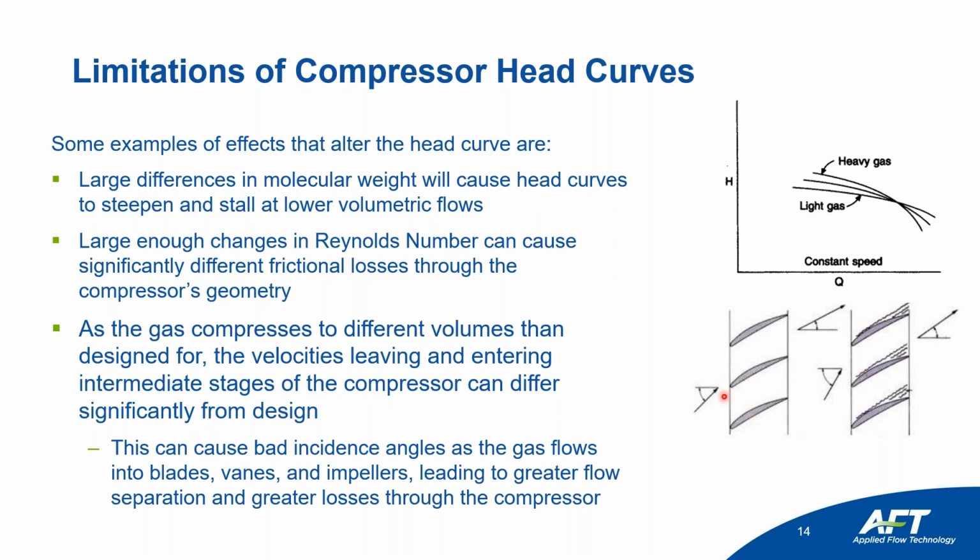and that's going to cause a different incidence on the rotor blade. Now, if that incidence angle is quite off, that can lead to greater flow separation and greater losses through the compressor.